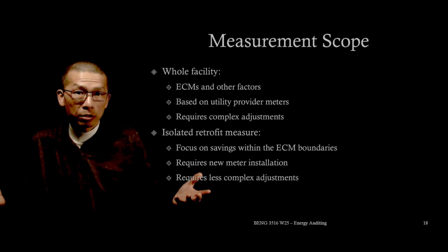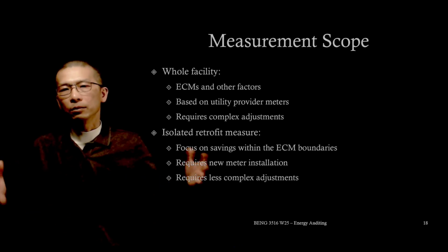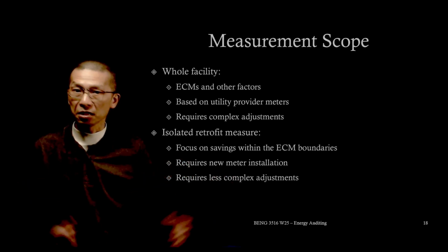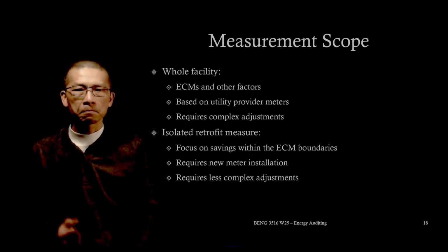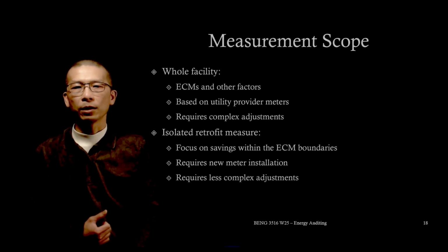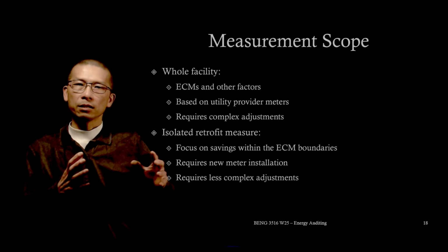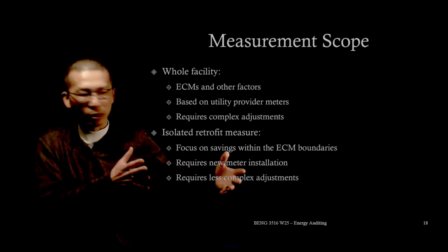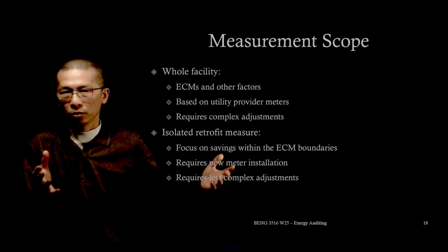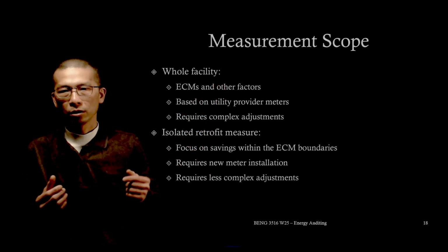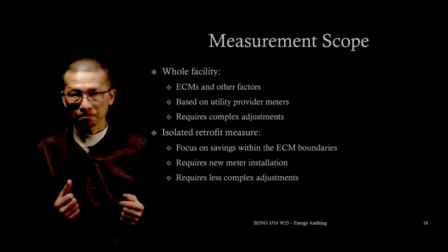But why is it used? Well, for large-scale projects where ECMs affect multiple systems, like HVAC upgrades and building-wide retrofits, and when we have sub-meters for different zones. Sometimes when sub-metering is not available, then the whole facility approach is when it's used.